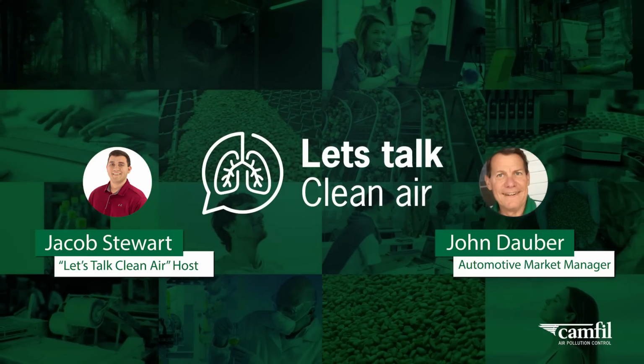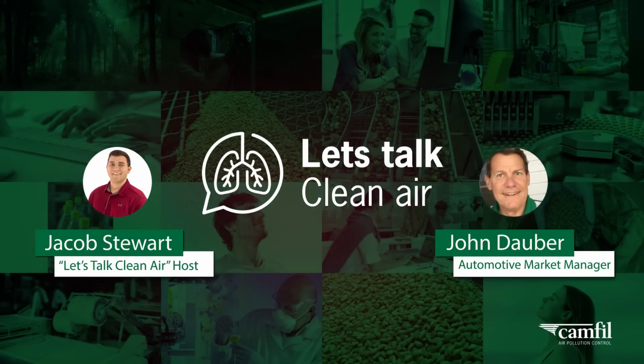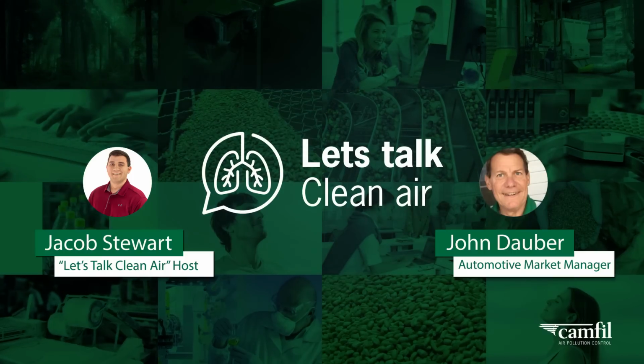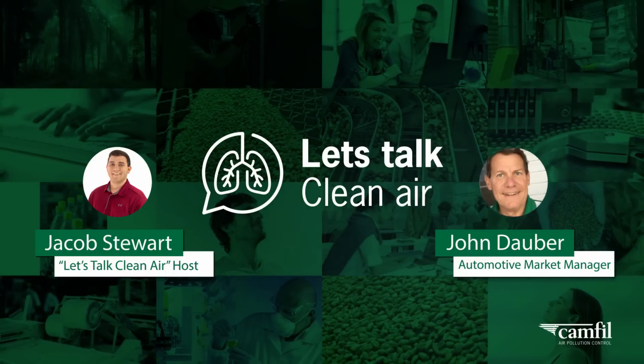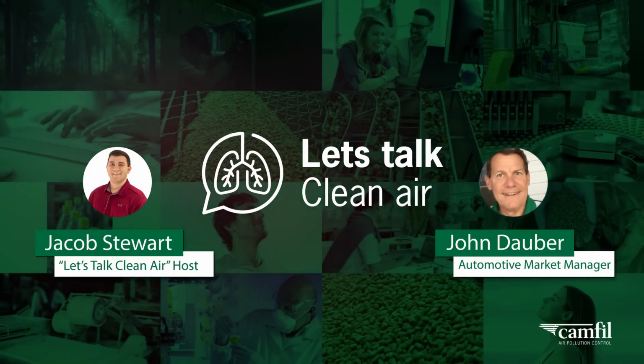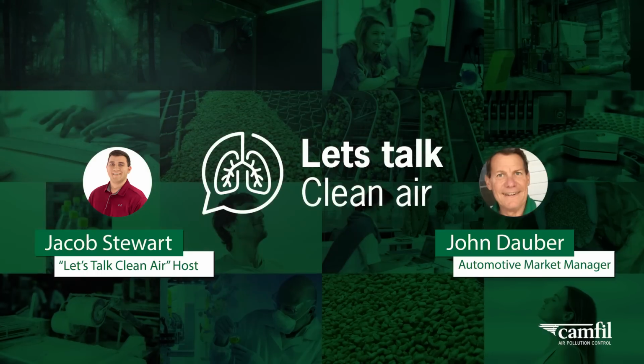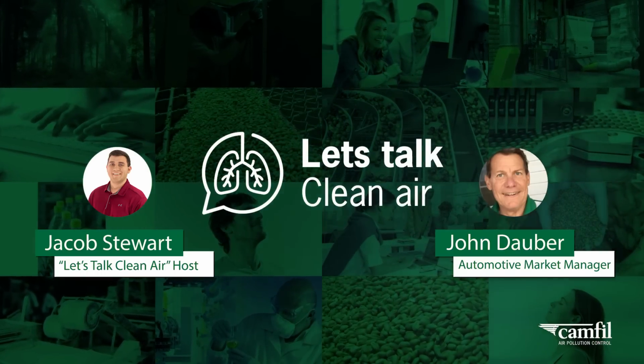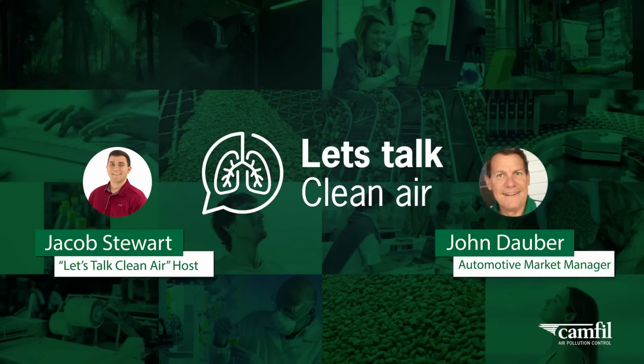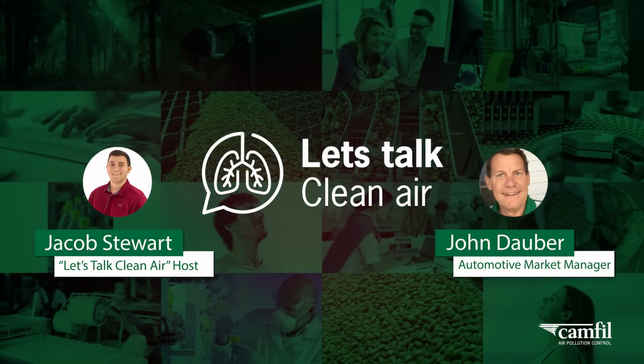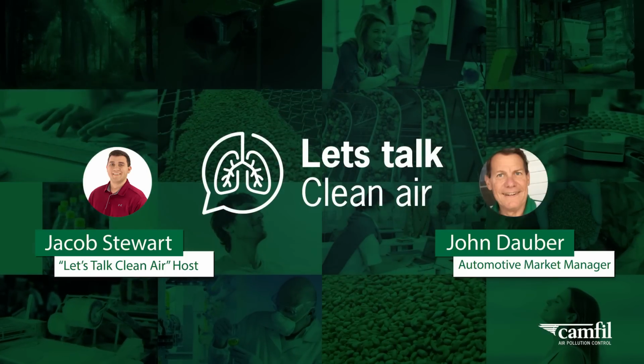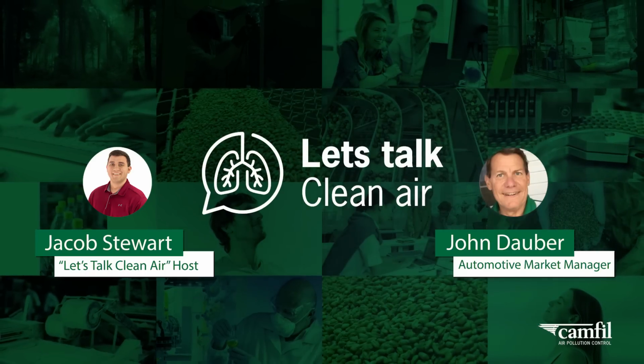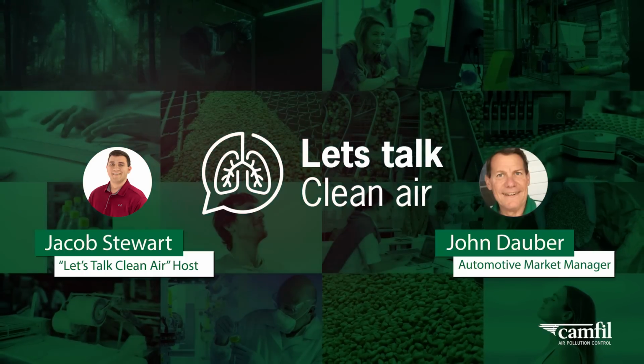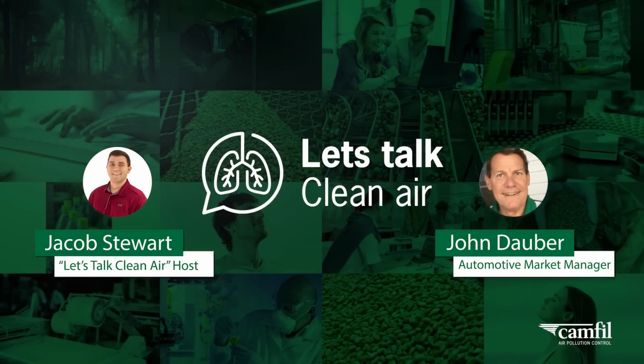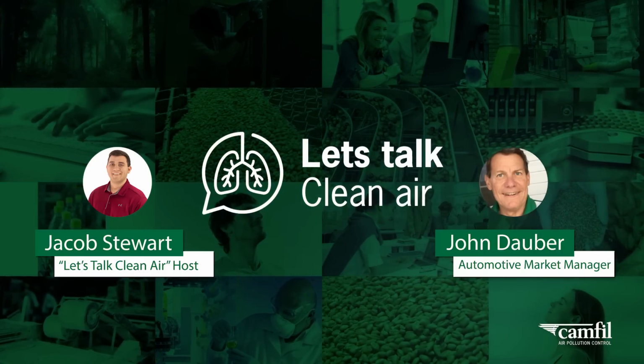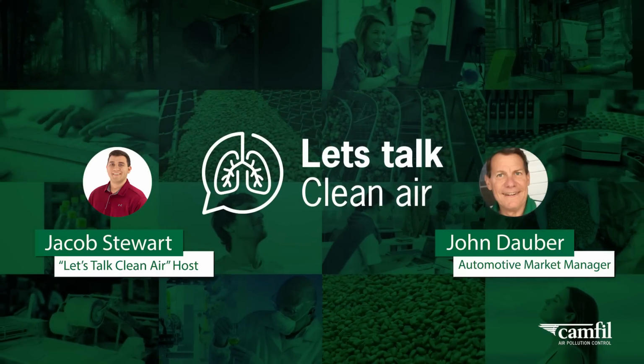And sometimes we stop the event with suppression before whatever gets started with some very sophisticated equipment. Sometimes it may just be relieving that pressure within that vessel or that dust collector so it doesn't become a bomb, basically. So there's a lot of ways that we could determine the type of equipment, but everything is really based on the KST value of the dust that you have tested. I think the cost for that is $2,200, something like that, to do the full test. Most companies will do that in a heartbeat because they need to know it's actually an NFPA requirement that you know the KST value of your dust in your plants.